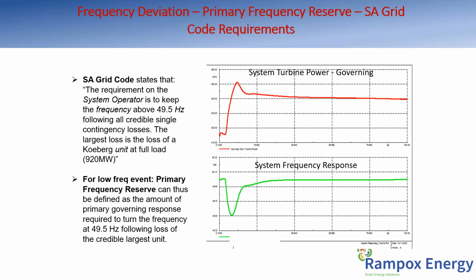That means the system operator needs to always have reserves that will help the system should they lose a generation unit at full load, because that is the largest contingency where frequency may dip too far. They need reserves, not necessarily exactly 920 — you have to do a study to determine how much they need to carry to arrest the frequency should that unit trip.